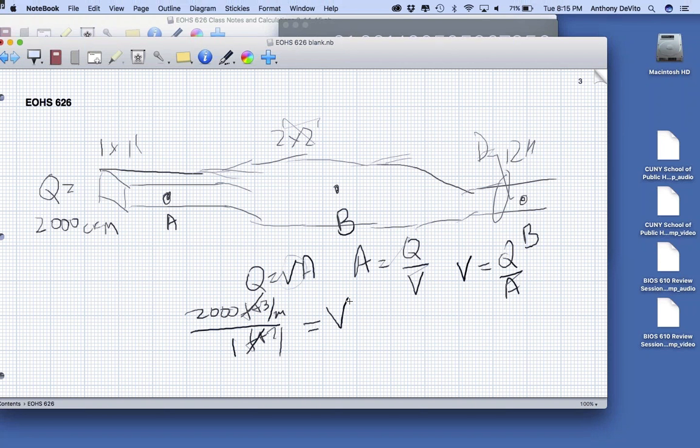Now remember, hang on a second. That's round duct, 12-inch diameter round duct. What's the cross-sectional area of 12-inch diameter round duct? We just worked it out, didn't we? 0.785 square feet. So it's going to be 2,000 over the cross-sectional area, which is 0.785, right? So this was 2,000 feet per minute. This was 500 feet per minute. And this now is going to be...